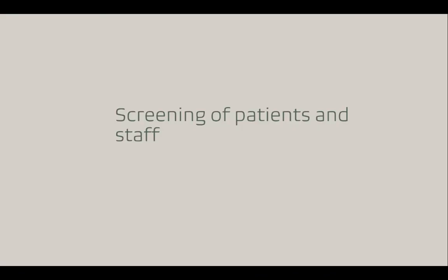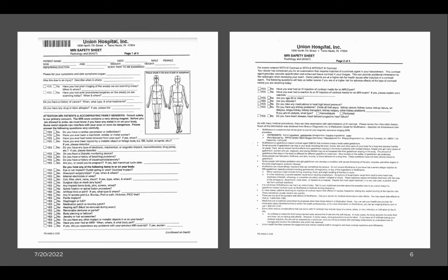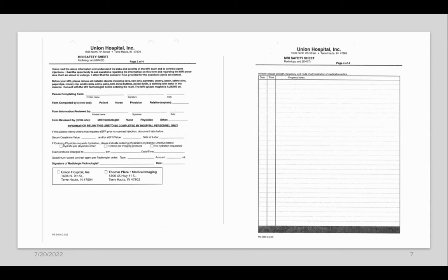Screening of both patients and staff is vital for safety within the MRI environment. All MRI patients are screened thoroughly prior to entering the MRI suite. The process starts with an MRI safety sheet to ensure that the patient does not have any medically inserted devices or external objects that are contraindicated for the MRI environment. For inpatients, this process begins with an interview from the nurse, and the safety sheet is sent to MRI. The MRI tech will then fully investigate the safety of any medically implanted devices and fully interview the patient prior to the MRI exam. Personnel will also be screened with a similar sheet to make sure that it is safe for them to enter the environment if they are doing so to care for a patient.